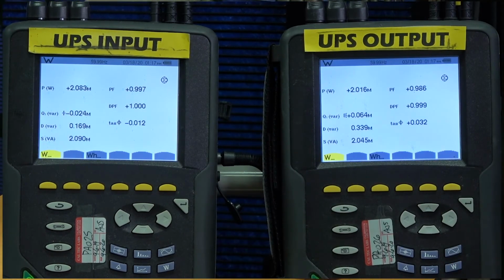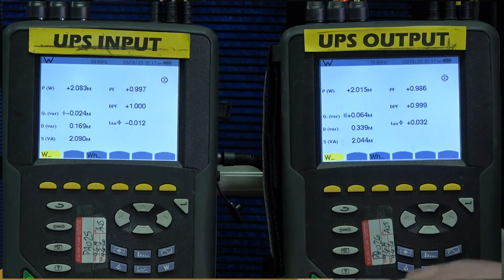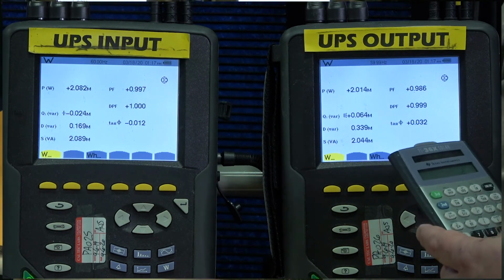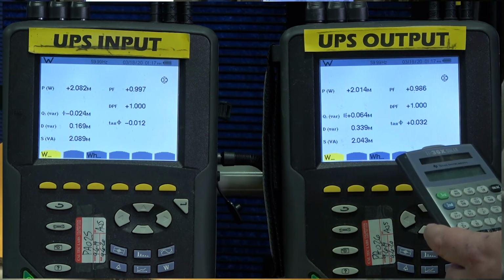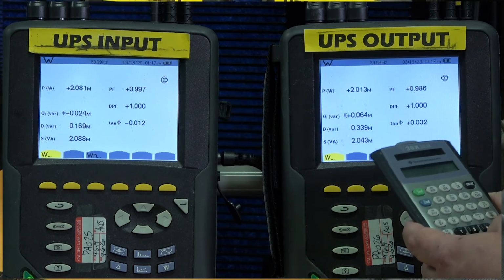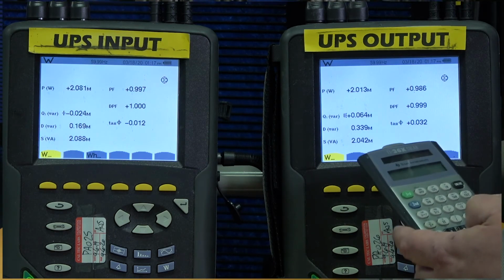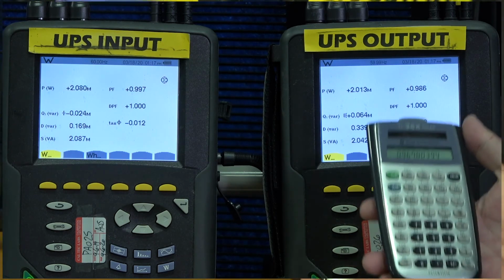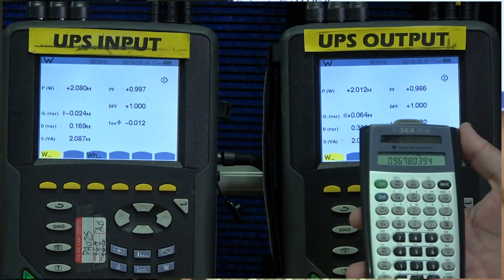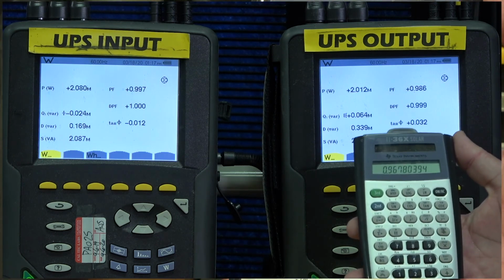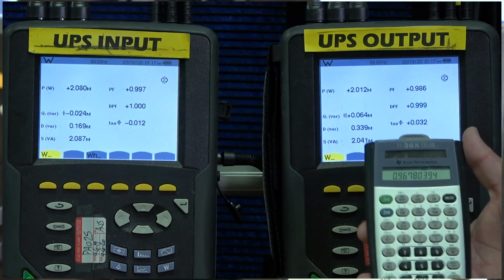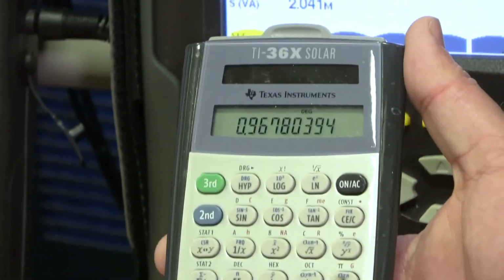Back to our power ratings, we can see we're at 2.014 megawatts divided by 2.081 megawatts. So about 96.78% or 96.8% efficiency at 100% load.